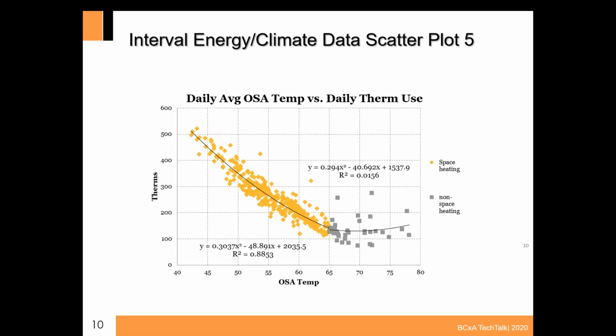It is weather dependent, that's true. What's the schedule of this facility based on this scatter plot? Yeah, 7 days a week. Lance is right: if we were shut off on the weekends, the gas use wouldn't go up with the heating load. There'd be a cloud down here at the bottom when the building is off, and we don't see that. So this is a 7 days per week operation.